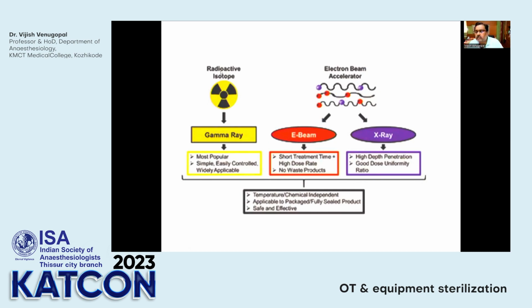So a radioactive isotope like cobalt 60 gives rise to the gamma rays, and this is the most popular one. The other one is using an electron beam accelerator, which can give either an E-beam or an X-ray. And the advantage is that in the electron beam accelerators there are no waste products, and it is a very effective form of sterilization. Well, the problem with this is you need specialized equipment, and it can cause radiation exposure. So we should be very careful. All radiation protection should be taken, and you should also have a dosimeter.